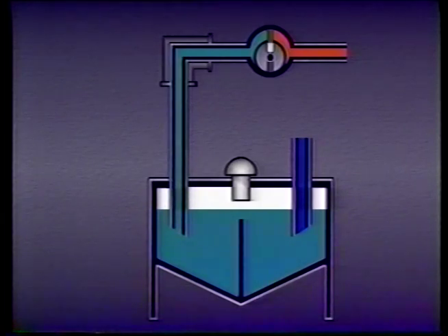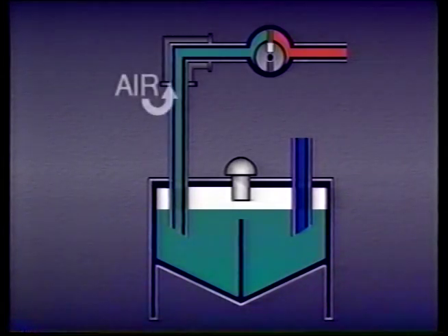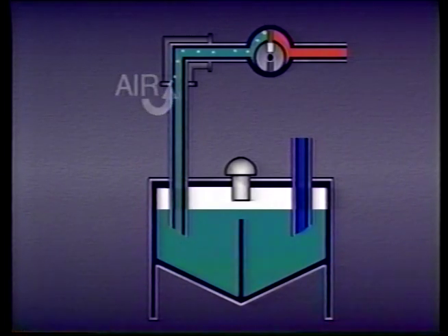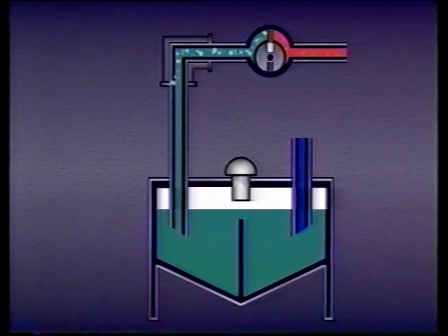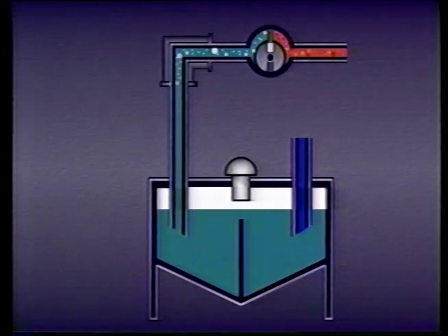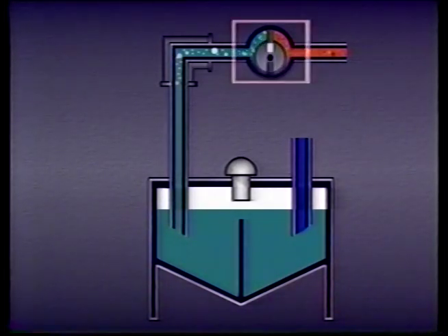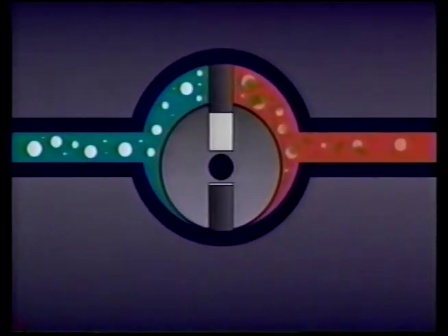Oxidation in the pump happens when air is allowed to enter the suction line through a leak or by excessive churning of the oil in the reservoir. In either case, the air forms bubbles which collapse when they are subjected to the high pressure at the pump outlet.